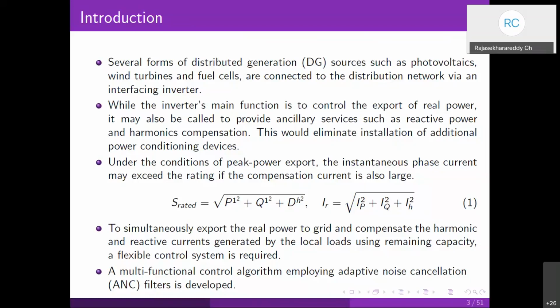If the inverter capacity is not being completely utilized, we can use the remaining capacity of the voltage source inverter for power quality purposes. That is the idea here. This way we eliminate the installation of additional power conditioner devices. When we use this inverter for active power generation along with power quality improvement through reactive power and harmonic current compensation, we need to consider the various power components that the inverter is going to handle in this situation.